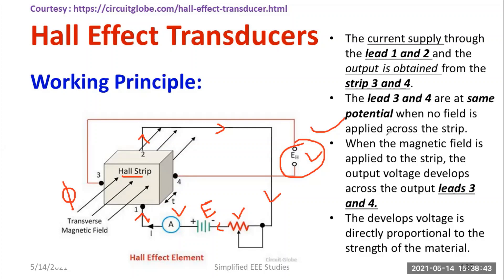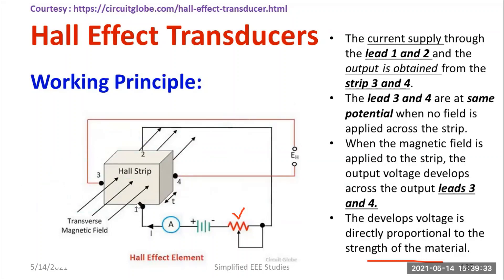Terminals 3 and 4 are at the same potential when no magnetic field is applied across the strip. When the transverse magnetic field is applied to the strip, the output voltage develops across lead 3 and 4. The developed voltage is directly proportional to the strength of the magnetic field. This is how the Hall effect transducer operates — we require a Hall strip, a continuous current supply, and a terminal to measure the Hall voltage.